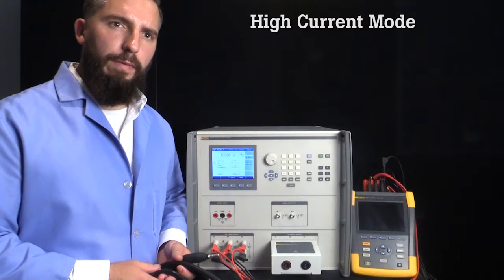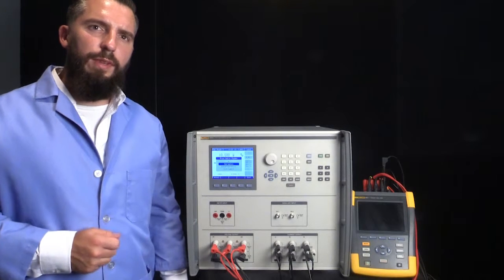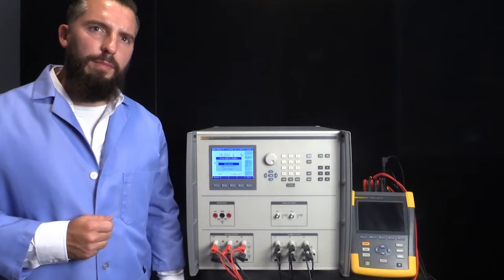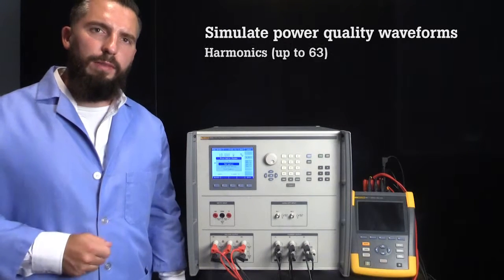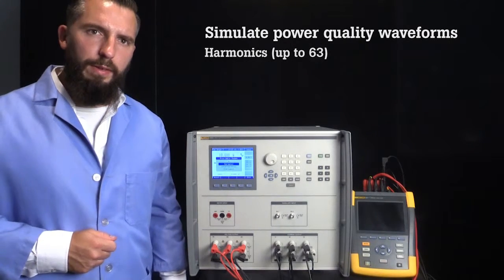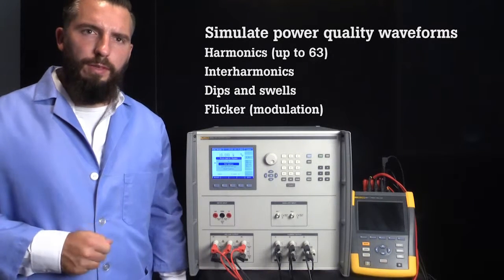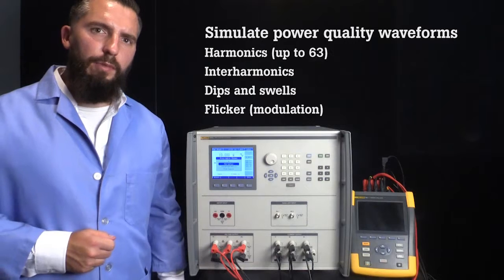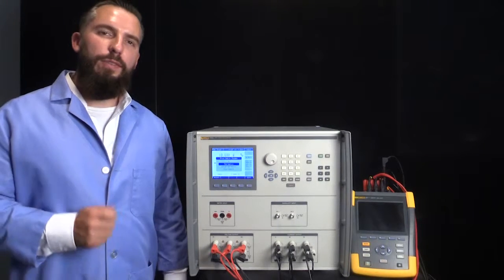The 6003A has unique advanced functions that let you change the output to accurately simulate these power quality waveforms: harmonics up to the 63rd harmonic, interharmonics, dips and swells, flicker or modulation. This functionality will be covered in more detail in another video.